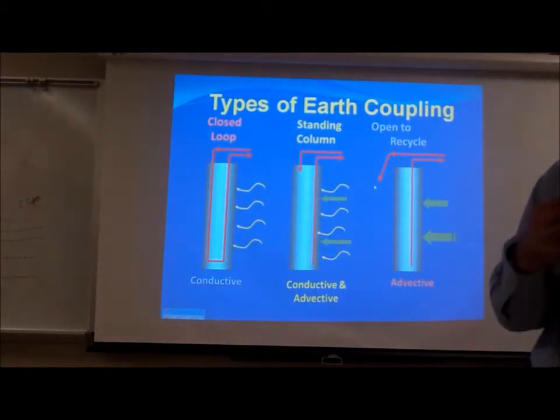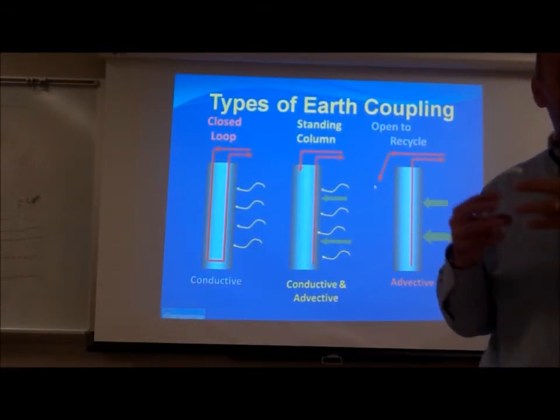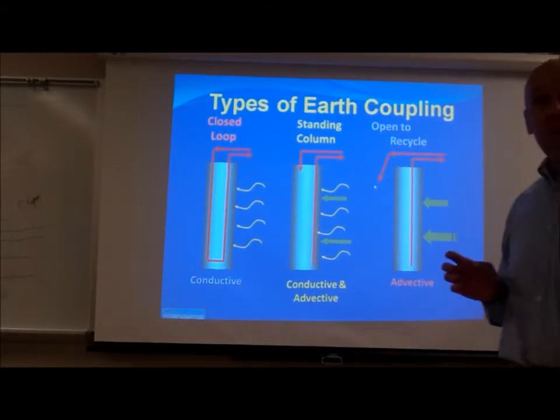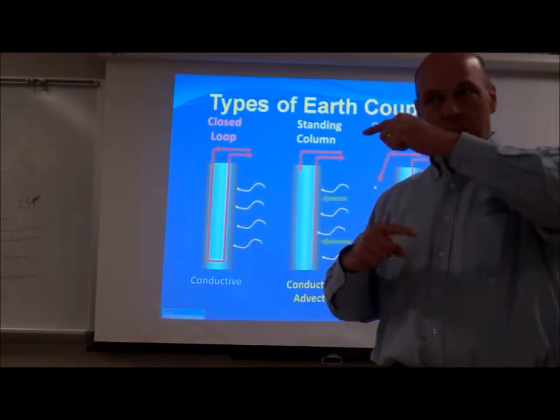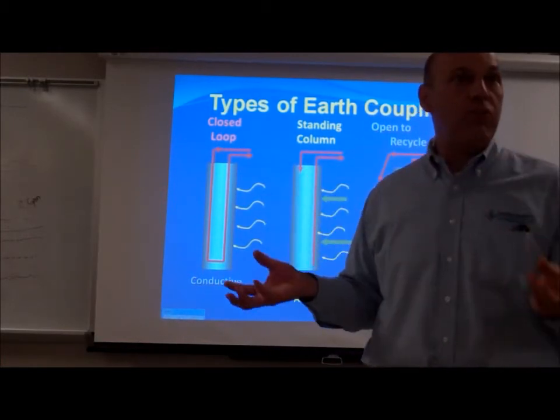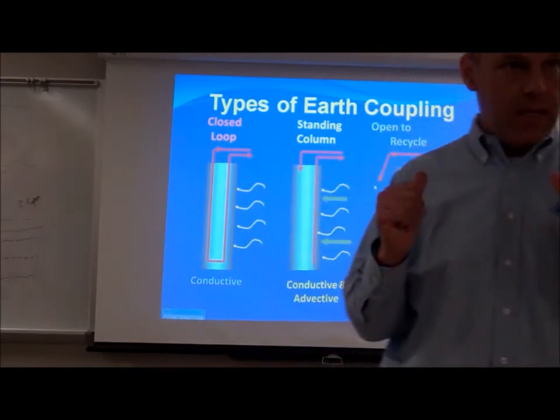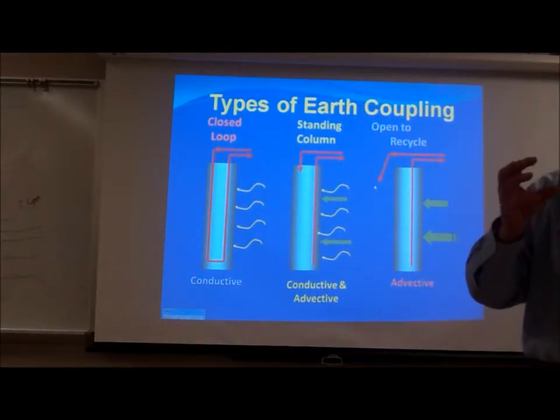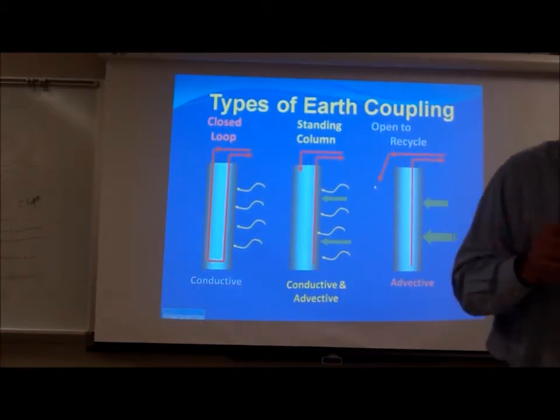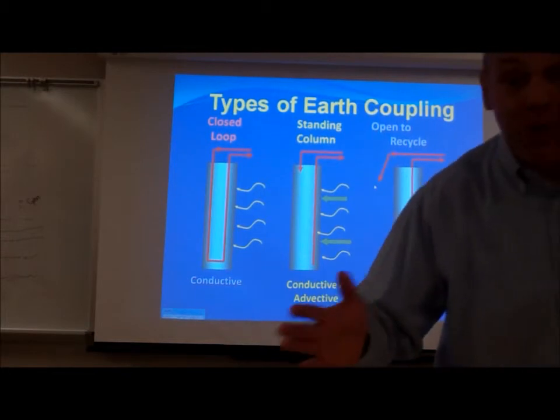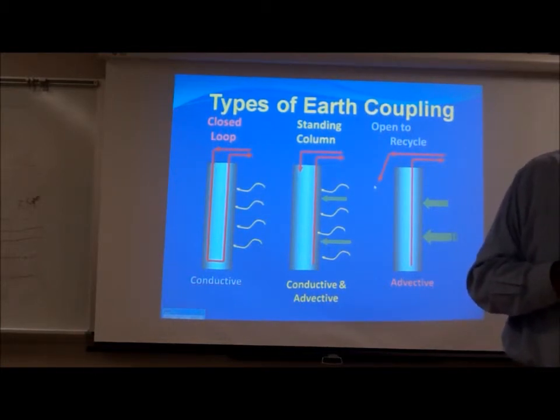Then I've got to look at pumping energy. As I create turbulence, I increase my pumping penalty. And as I look at how much asset I have to put underground, I look at my initial investment. So a closed loop designer will look at all three of those things: how much pumping penalty am I going to face, how much asset do I have to buy, and where do I have to go in my design to get turbulence and a good heat exchange? The same laboratory settings by which those units are rated also identify the sweet spot of closed loop design — just enough pumping energy to achieve turbulence, and just enough closed loop asset, so there's no missed opportunity on parasitic activity on either the source side or the load side in that rating.